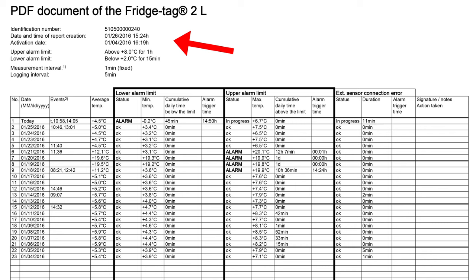At the very top, we see the serial number of the device in the report, the date the report was generated, and importantly, the date this data logger was activated, which can be helpful when reviewing for recalibration. It also shows the alarm settings and that the logging interval is every five minutes on a Fridgetag 2L.